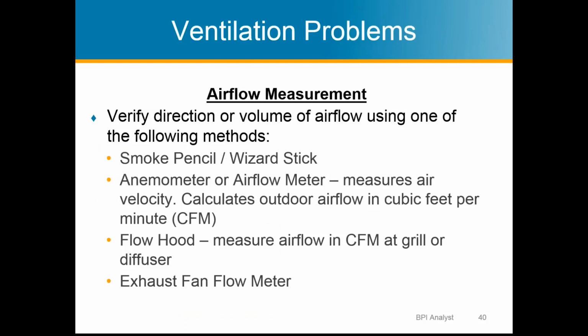And mentioning ventilation systems, it is required and of course good practice that any exhaust ventilation system's exhaust air completely leaves the building shell. So oftentimes, like in a bathroom, that's going to go through the roof or maybe a sidewall in the attic area. But it is required that the exhaust air leave the building completely, the envelope.